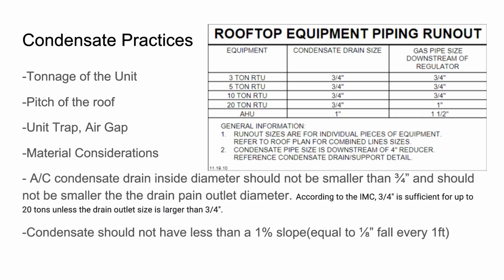The pitch of the roof, obviously you should have a 1% slope, which is 1/8 for every foot. So if you don't have that drainage, that pitch, if you're trying to go uphill because the end of the roof is flaring because the insulation was installed a certain way to go to a roof drain, you obviously can't go that route. You can't go upstream around the unit. If their drain is on the top side, you can't go in the opposite direction of the slope. You have to follow it all the way down. Pretty common sense, water don't drain uphill. So just make sure that you're installing it and it has enough pitch to actually move the water out of the drain pipe.